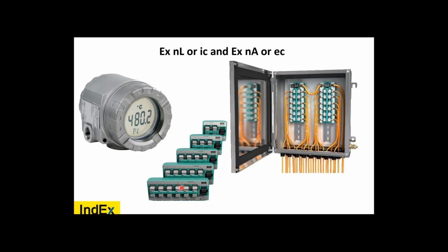So now the IC goes inside the EC, which feeds the IC instrument. Basically, with these 4 different protection techniques, depending on the year of installation or manufacturing, you have a multitude of options. If you see an EXNA certified terminal like this, it must go into an NA enclosure, IP54 minimum.